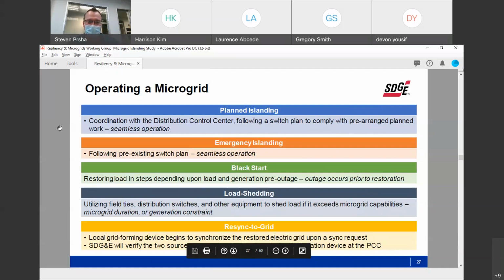It's important to slowly pick up the load because, especially in a case like Borrego where you have almost 3,000 customers to pick up, you can't do it all at once. As Devon mentioned earlier about cold load pickup or inrush, there are times when picking up load you can see up to 3 times the amount of load you saw prior to the outage.